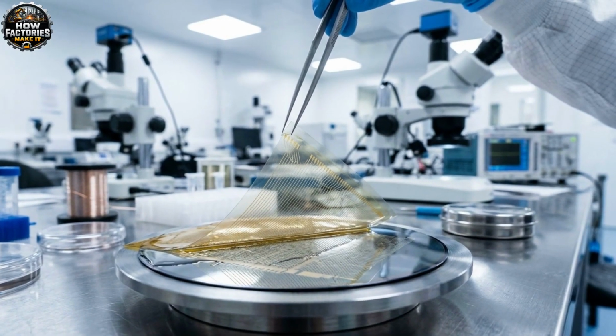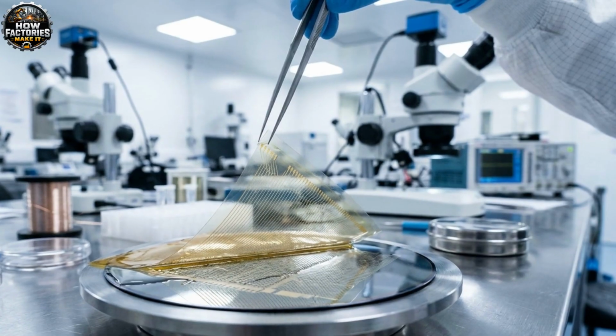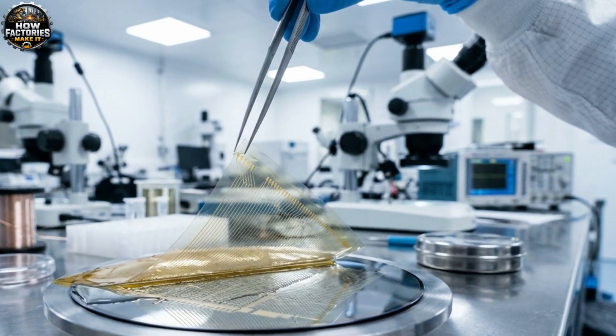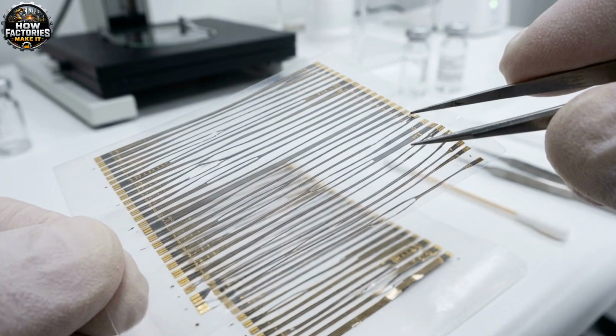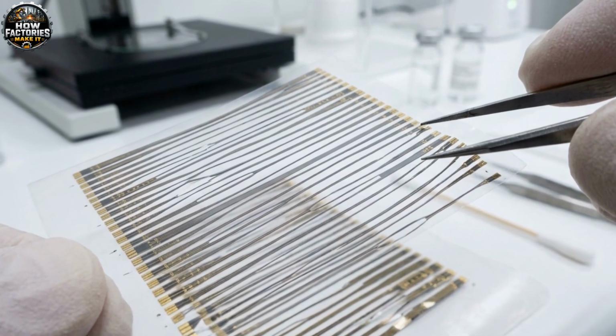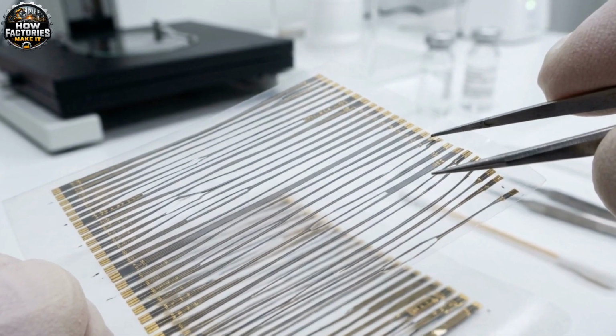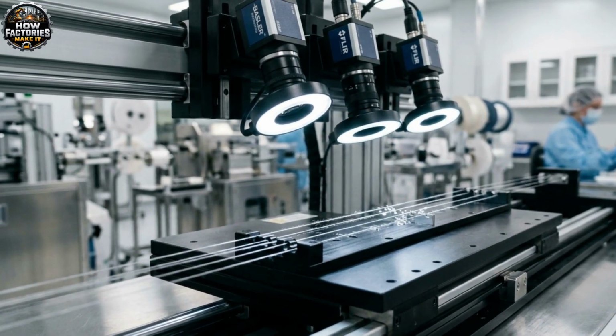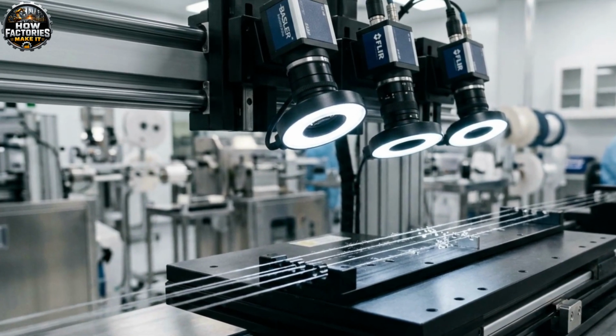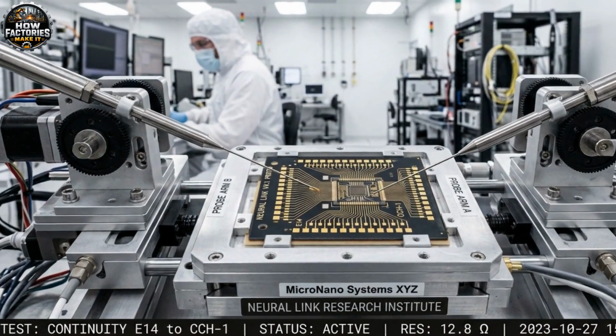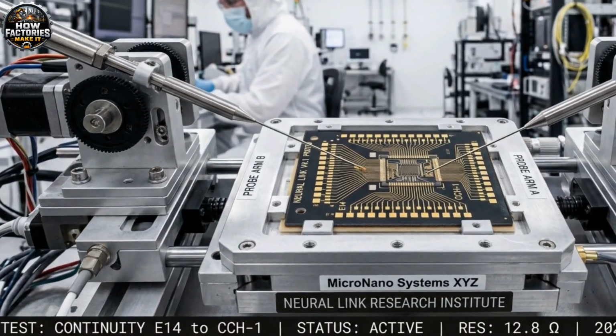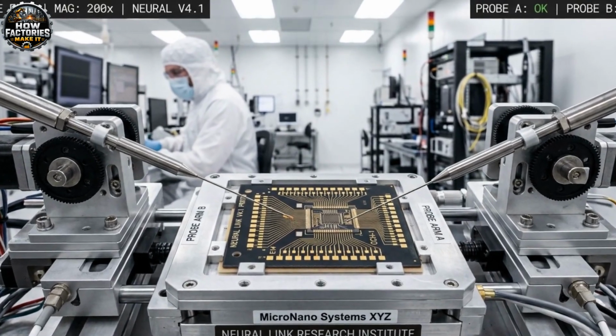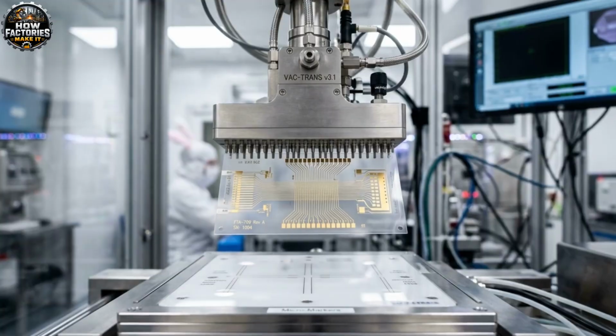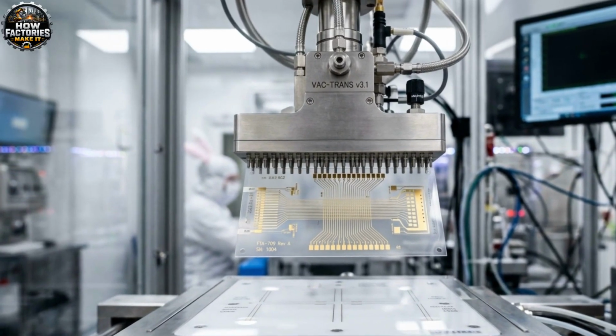After the thin film structure is complete, the thread array must be separated from its manufacturing wafer without stretching, folding, or tearing it. A carefully controlled release process removes the sacrificial material holding the array to the wafer. The individual threads remain arranged on a temporary support film so they do not become tangled. High-resolution machine vision cameras scan along each thread. The inspection system looks for cracks, damaged electrode contacts, irregular edges, and breaks in the conductive traces. Electrical continuity tests confirm that signals can travel from each electrode to the implant's connection area.